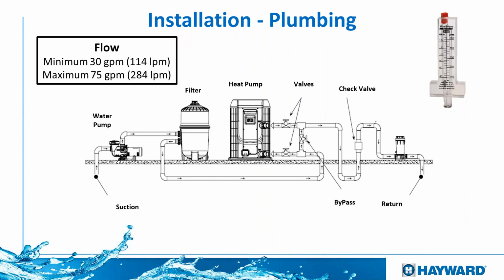By the way, when we see this kind of plumbing situation, I want to mention a couple things. First of all, it will be recommended to put a flow meter so we know what type of flow we're putting inside of the heat pump. The minimum is going to be 30 gallons per minute, and the maximum is going to be 75. So I recommend we don't put it to the minimum, because after the filter starts getting dirty, that minimum is going to become even lower. So we'll be going below the minimum, which is going to cause the heat pump to shut off because of not enough flow. Now, as for the maximum, I would also recommend we don't go to the maximum, and put some kind of bypass. I always tell customers, if you have a 1.5 horsepower pump or bigger, definitely put a bypass, and depending on the size, you may want to open it more or less.